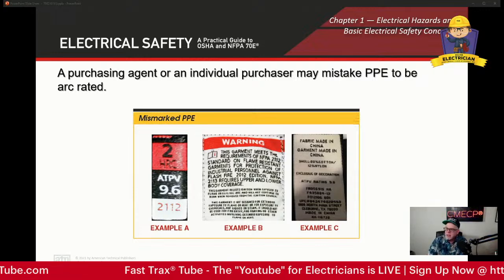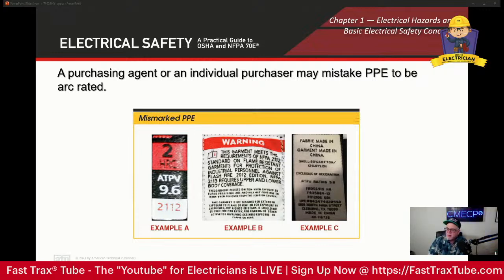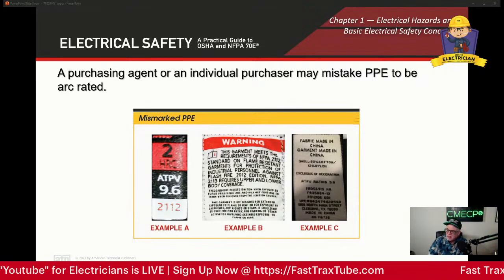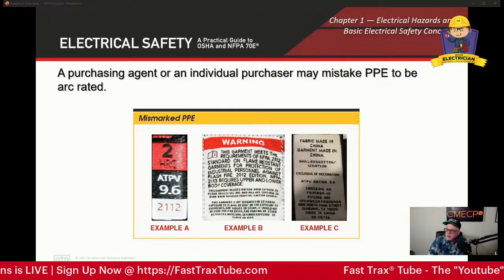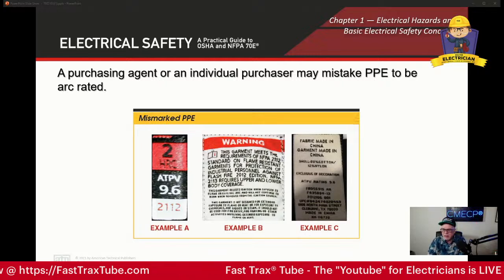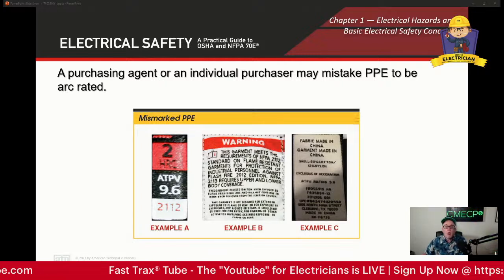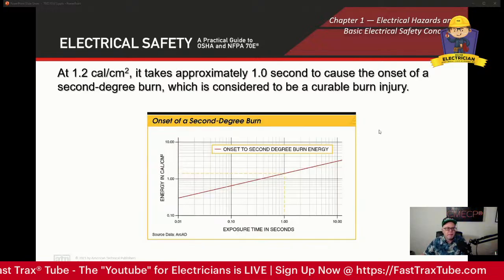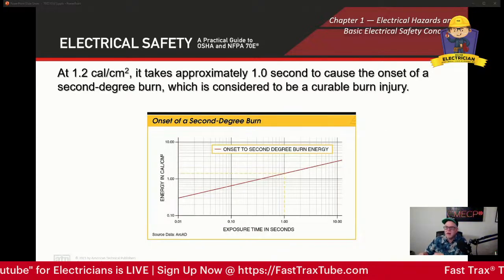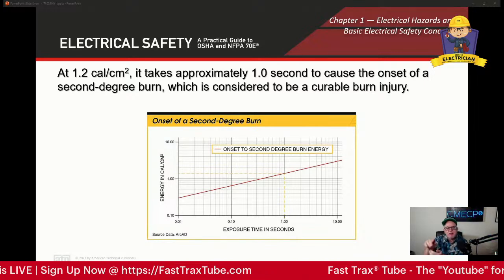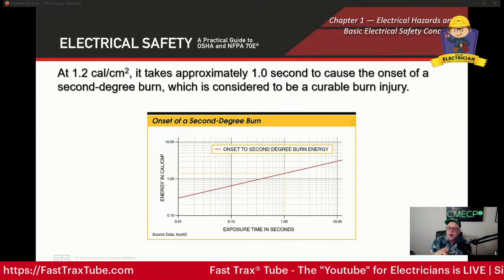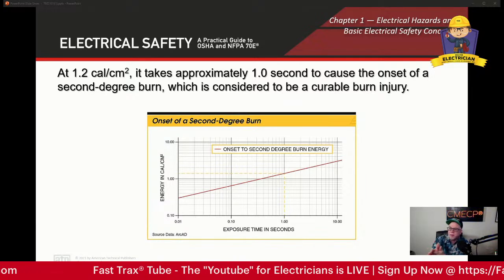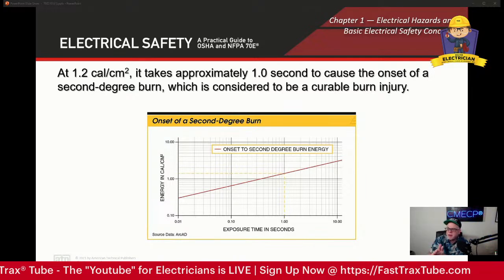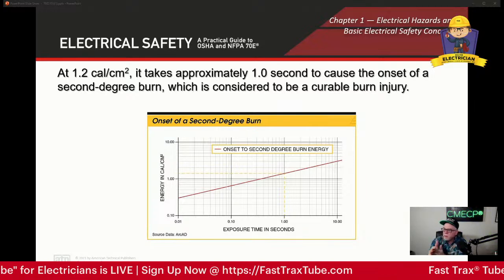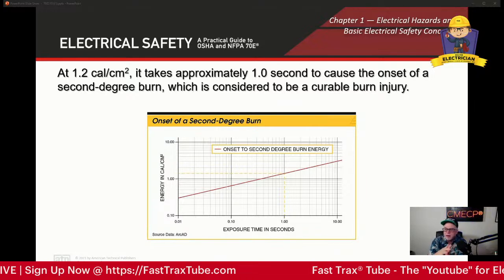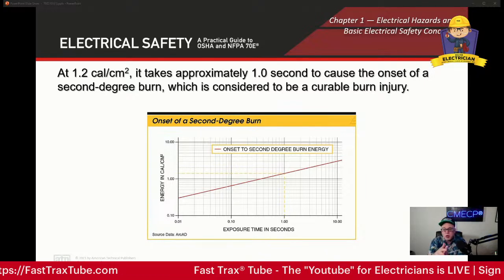Now, PPE can be rated with both NFPA 2112 and ASTM F1506, but both standards must be listed on the label. So always look for that when you're checking out your equipment. Now we're looking at this rating here. Per NFPA 70E, an arc flash boundary is an approach limit at a distance from a prospective arc source within which a person could receive a second-degree burn if an electrical arc flash were to occur.